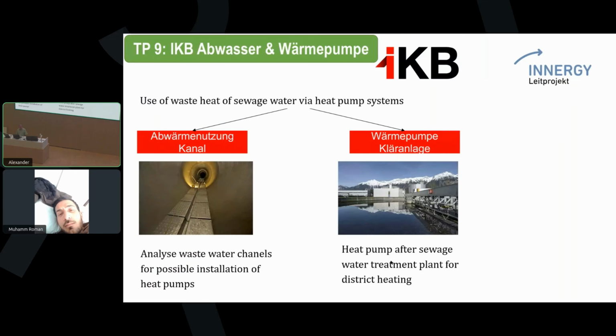Last but not least, we also try to use wastewater. Sorry, I forgot to translate: the waste heat from the sewage channel. As you can see here, there are some heat exchangers in the channel where the wastewater is flowing into the sewage plant. A heat pump already exists, which produces heat and sends it into the district heating network. And there is the plan to have one at the sewage plant. It was quite new for me that the water going into the plant and all the bacteria produce quite a lot of heat, so the water going out of the plant is warmer than coming in. So there is huge potential to use heat pumps to make heat recovery with that.